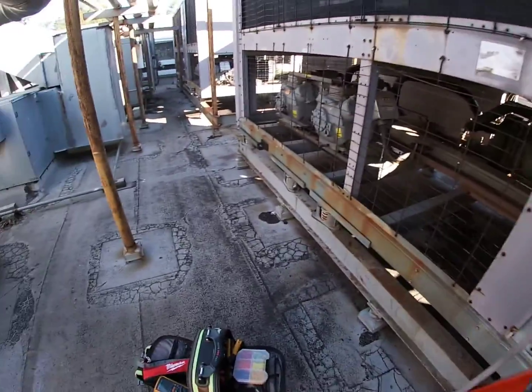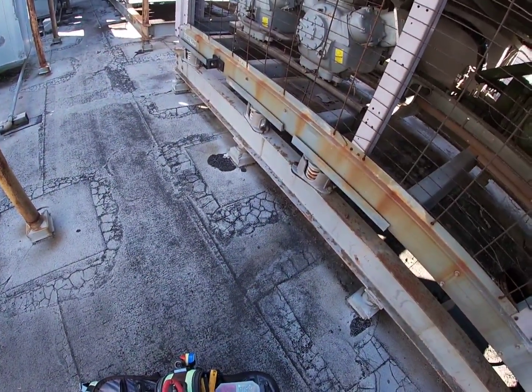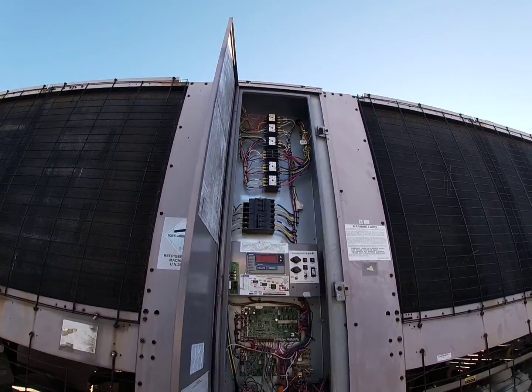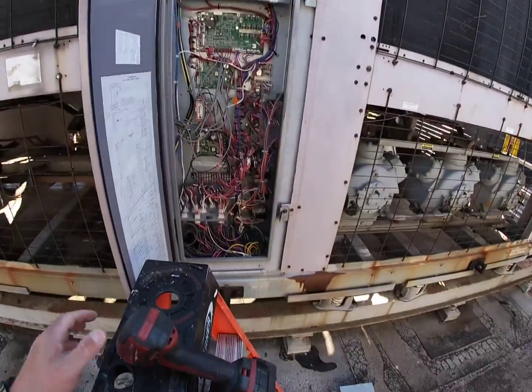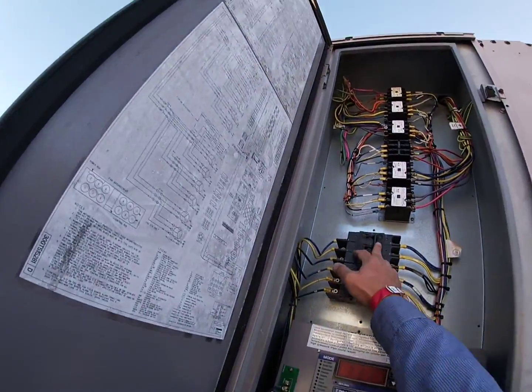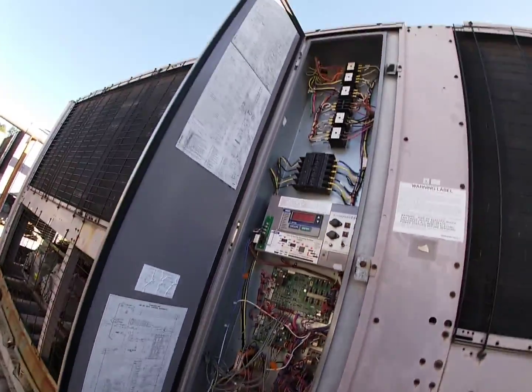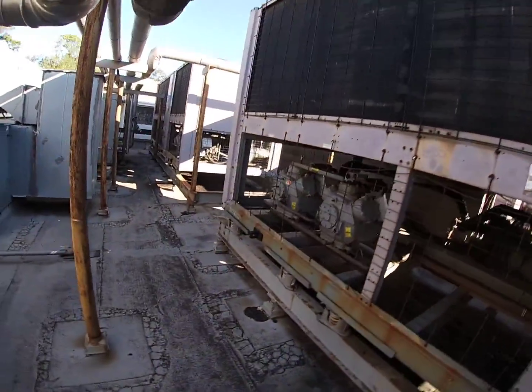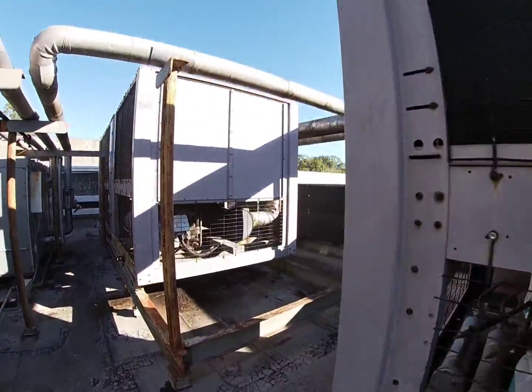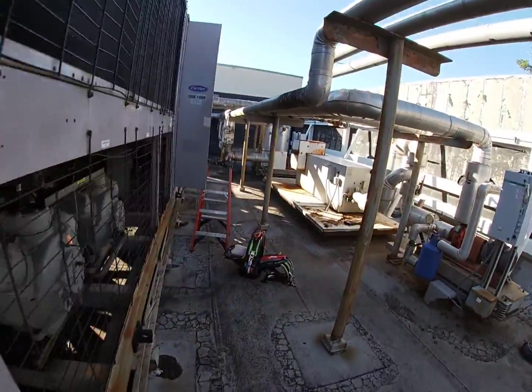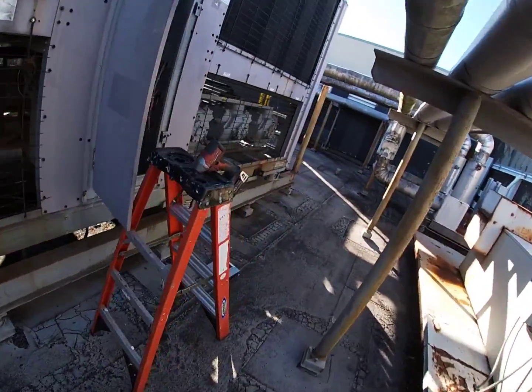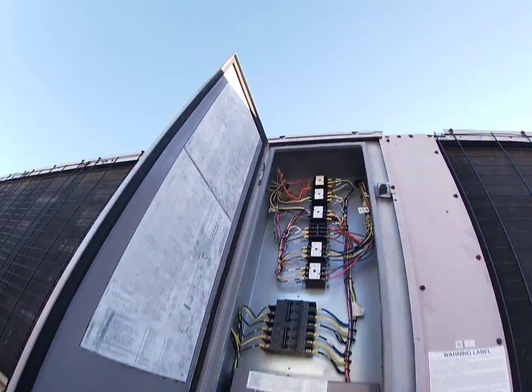Now what we'll go ahead and do is turn this thing on here and turn that breaker back on. We'll hit the main disconnect, put it in test run, and run the condenser fan motors to make sure we don't have any other problems. Actually, before I do that, let me make sure my wires up here are taken off so they're not touching anything.